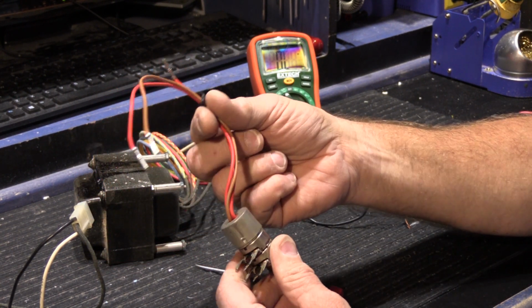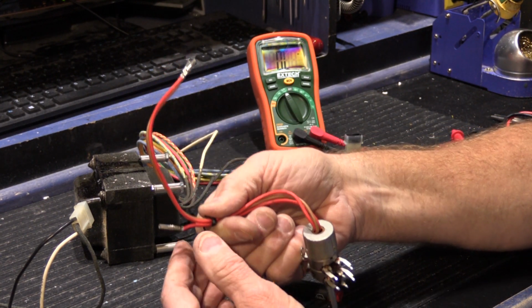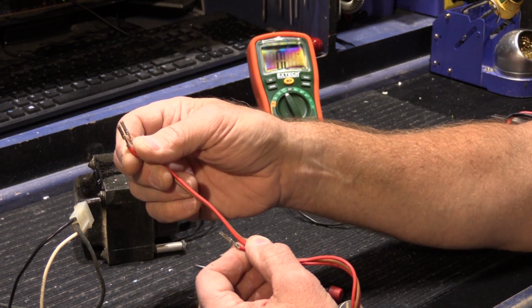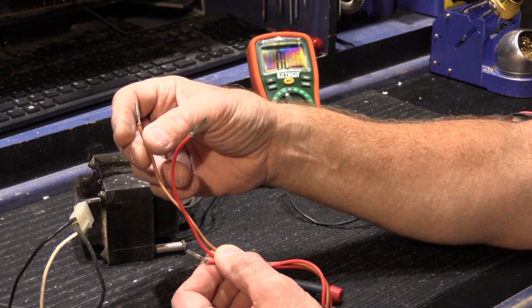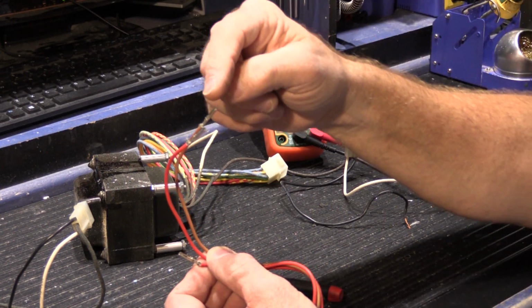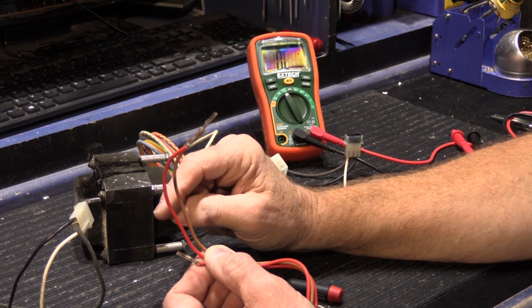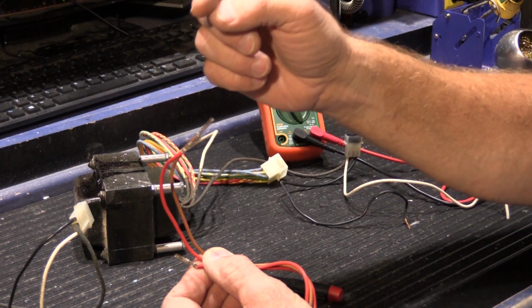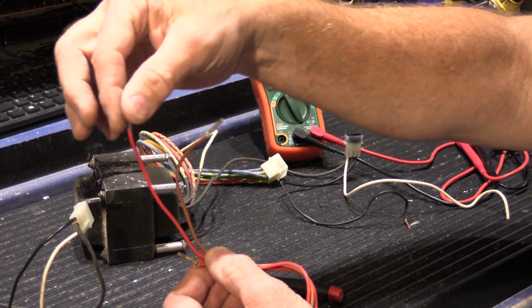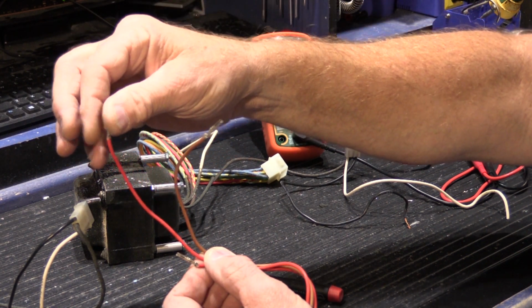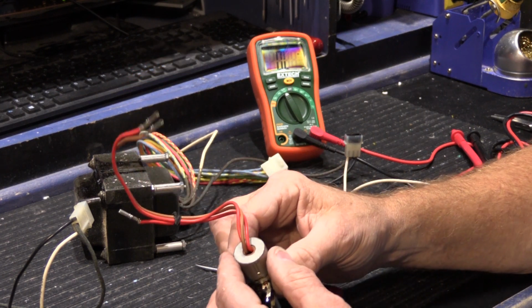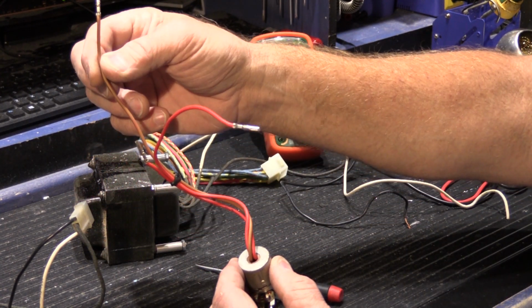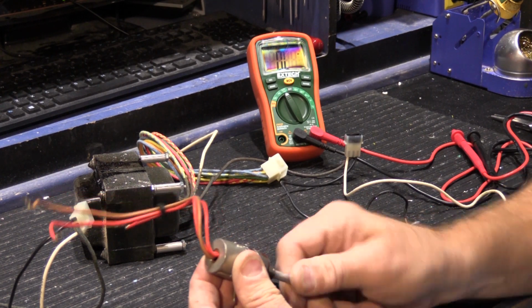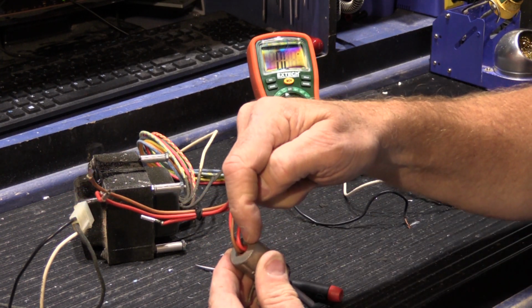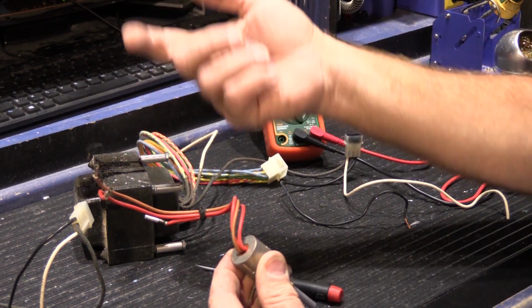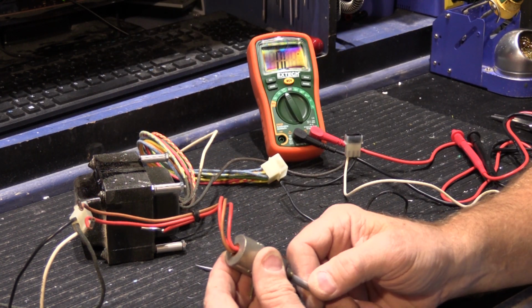These wires here are high voltage wires, and basically the installation works like this: you're switching the hot leg, the black leg, through the switch. The neutral is wired up to the transformer permanently. The hot lead, the black, comes in on the red wire to one contact in the switch, and then out the brown wire to the junction in the wall housing. When you turn the switch on, it closes the connection and the power flows, the transformer turns on, and your system works.